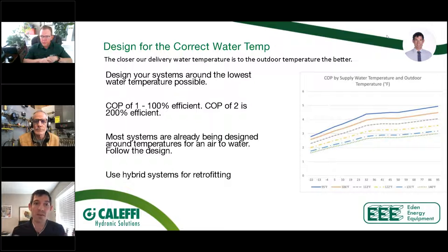So when you see AFUE on the side with boilers, that's assuming that you're doing everything to the peak of that chart. And that's the same thing with heat pumps: if we want to have these heat pumps shine, we need to be using the lowest temperature water to do the distribution in the building. And that's how you're going to see the COP creep back up.